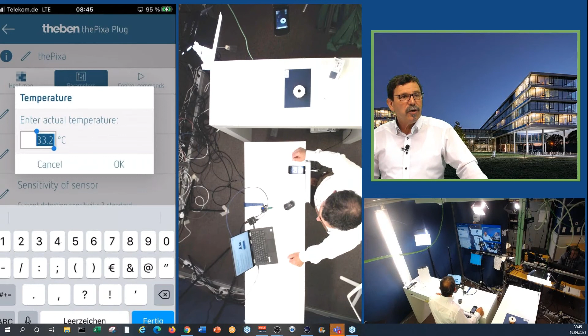But don't wonder, we have cameras in the area of the sensor - it's on the ceiling, measured on the ceiling, and there's a camera close by, and that's the reason why we have currently a rather high temperature measured. But you see here, if you do an offset and measure the real temperature, the current real temperature in our area is 23. So you can do internal calibration if needed.